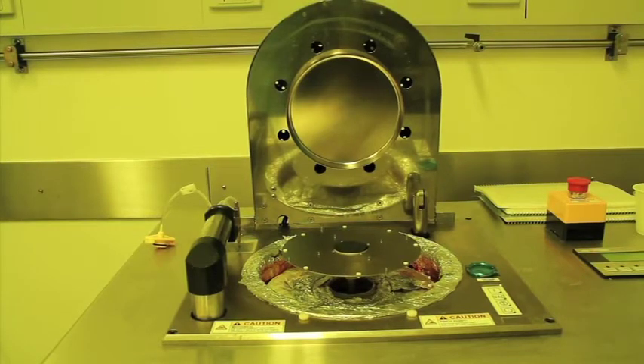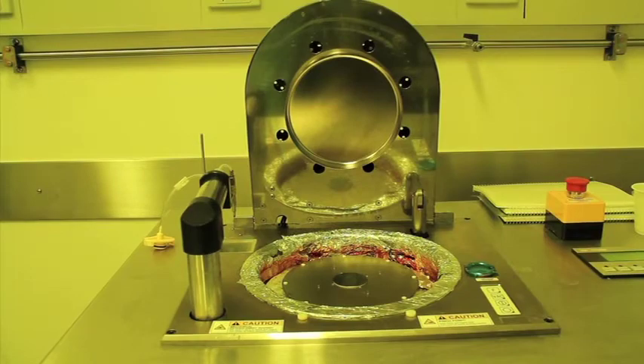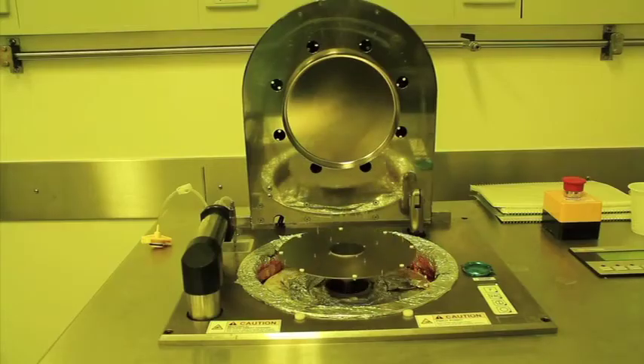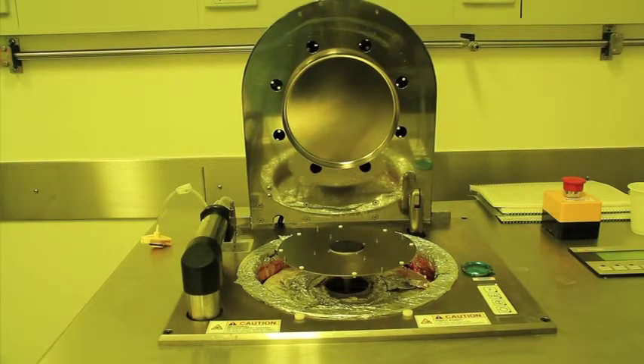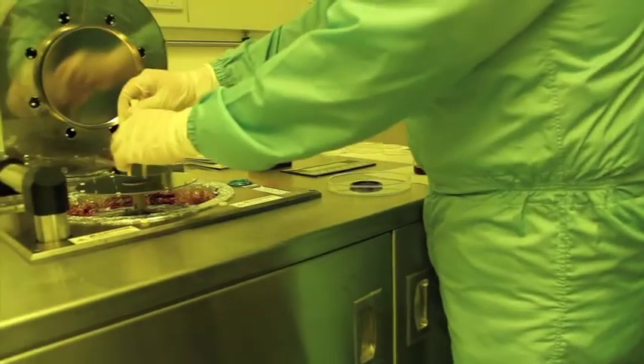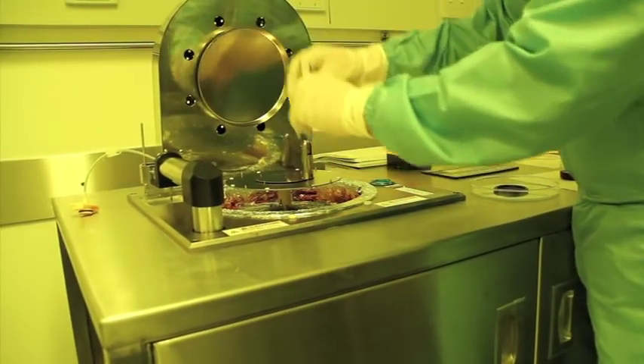Test the spin coater by using the dummy wafer. Make sure you check the vacuum is working by pressing VAC and looking at the pressure gauge on the right hand side of the spinner. Press VAC again to release the vacuum. Remove the dummy wafer and carefully place the silicon wafer into the spin coater using the tweezers. Ensure the wafer is within the four pins.